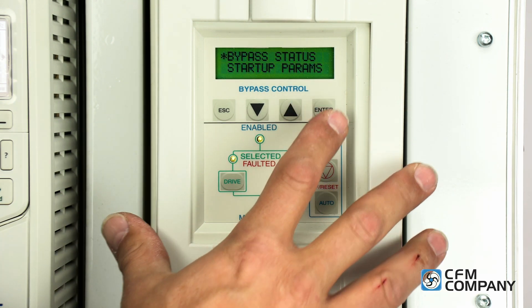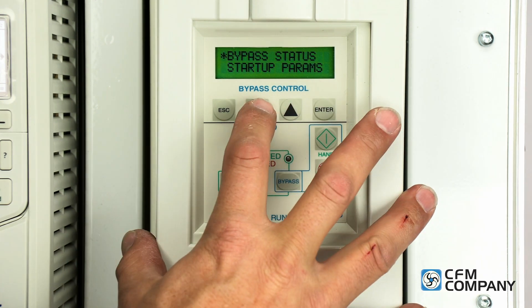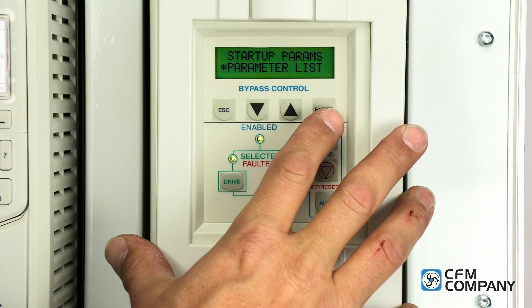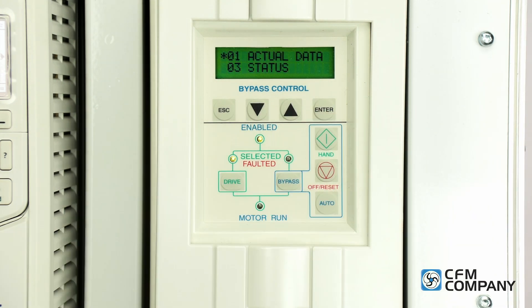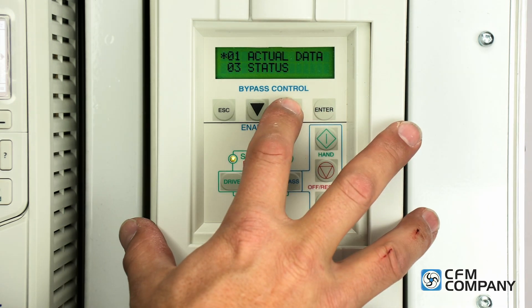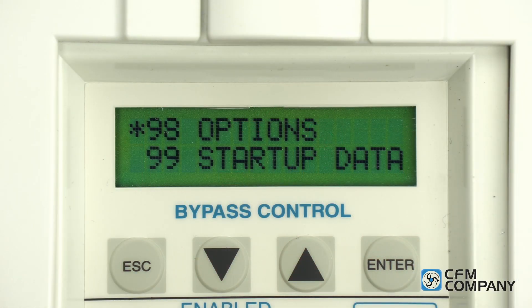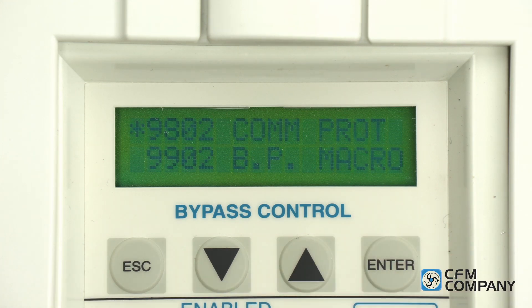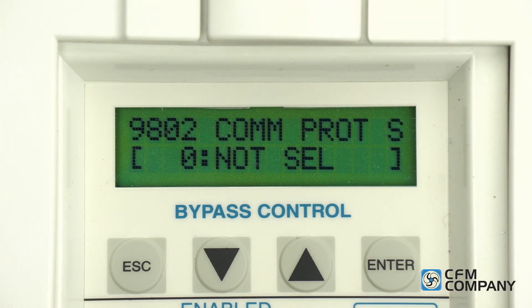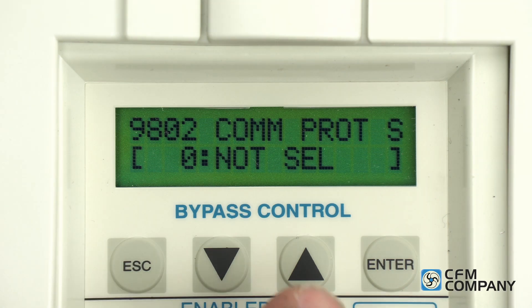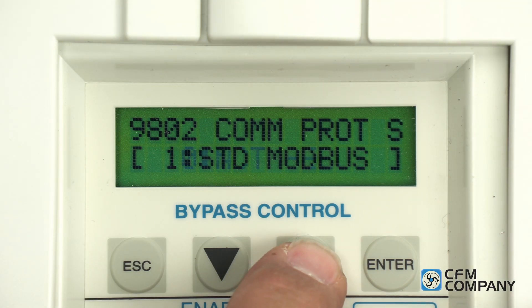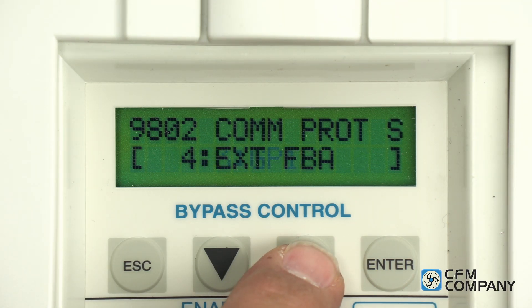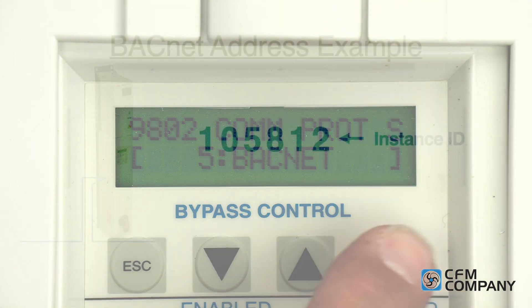Press enter. Use the down arrow to highlight the parameter list menu and press enter. Use the up arrow to highlight group 98 options and press enter to select. Parameter 9802 com protocol is shown. Press enter to edit. The screen will show brackets indicating that the value can be changed. Use the up arrow to select option 5 BACnet and press enter to save the selection.